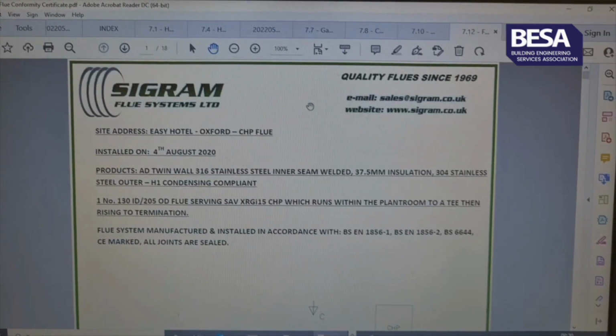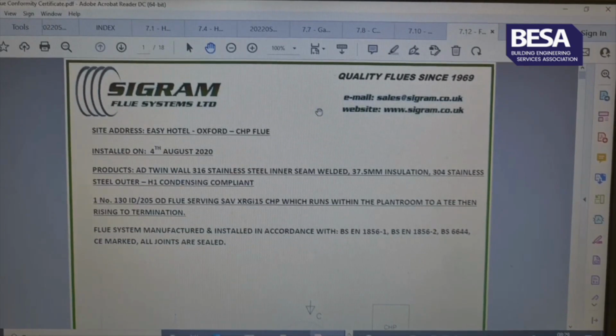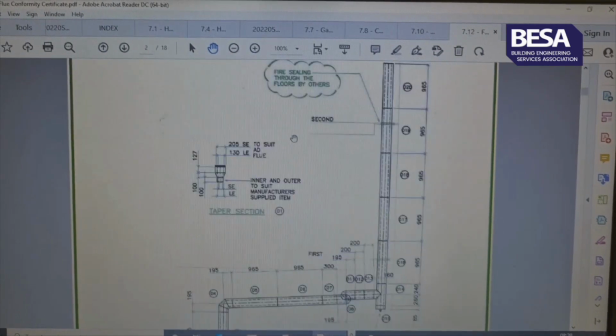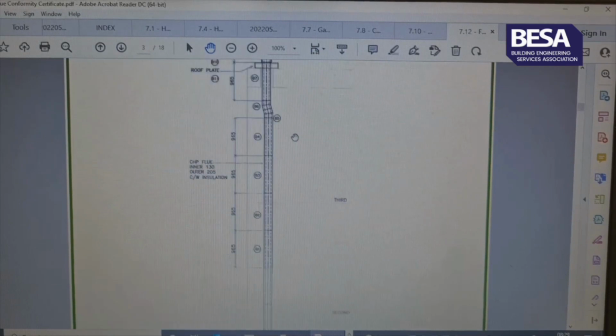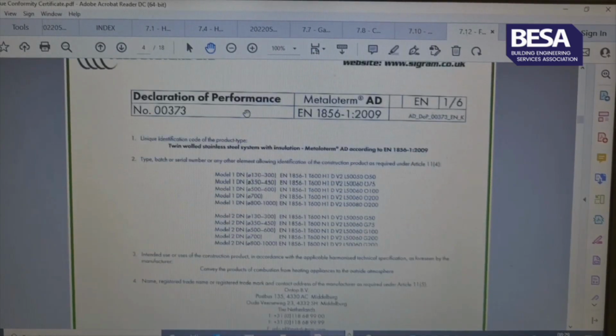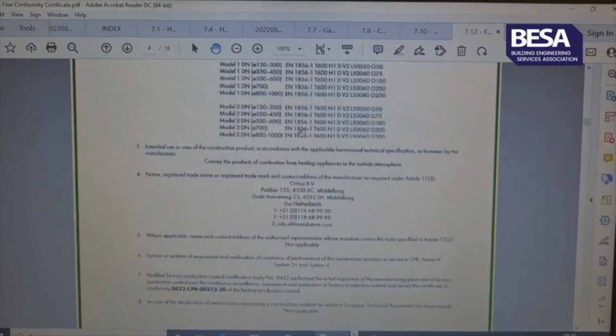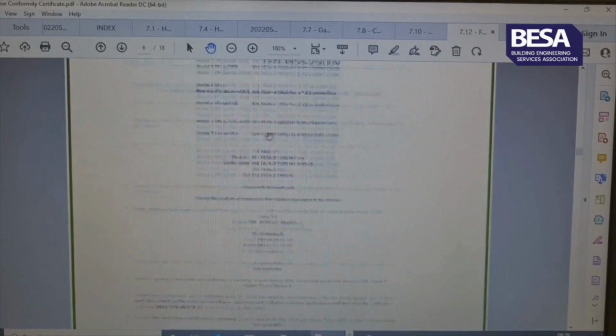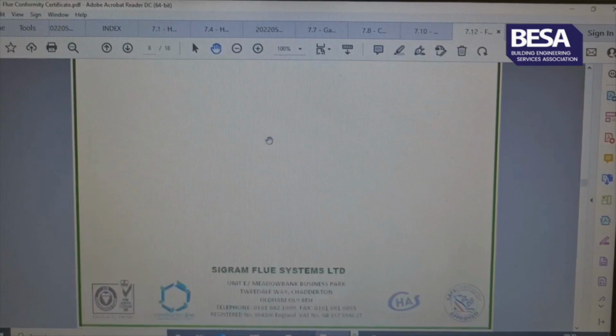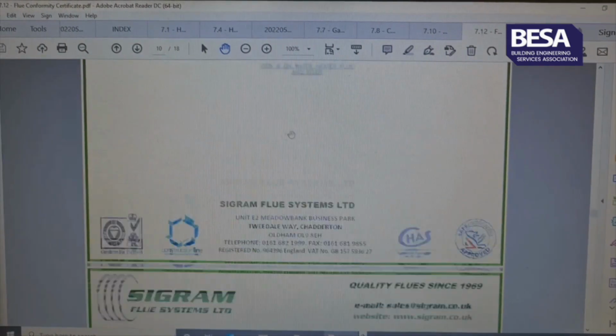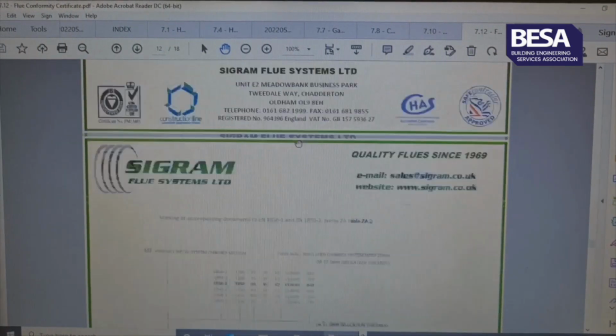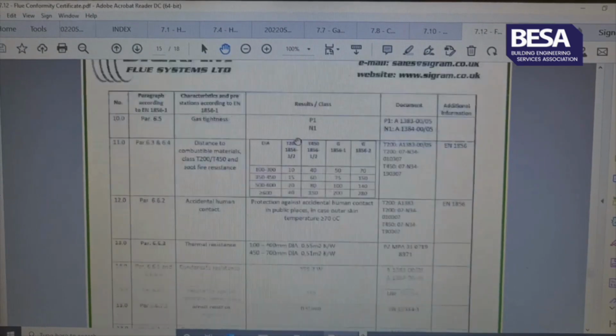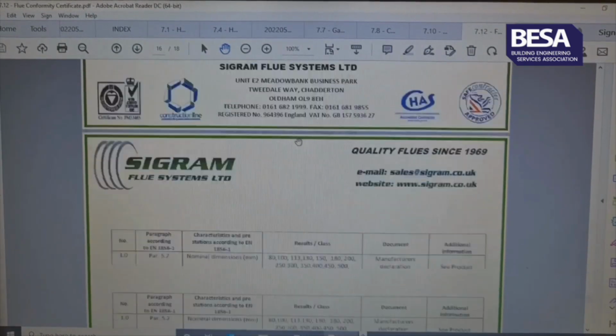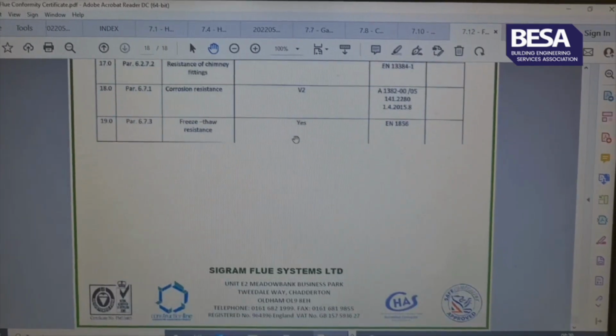Next thing we're going to look at is the flues. A couple of Sigram Flue Systems installed the flues. So there's two flues, one for the gas-fired water heaters and one for the CHP. And they did a full set of as-built drawings. And then you've got their declaration of performance and all their calculations to prove that the flue is up to specification. Again, all these documents are actually within the O&M manual that the client has.